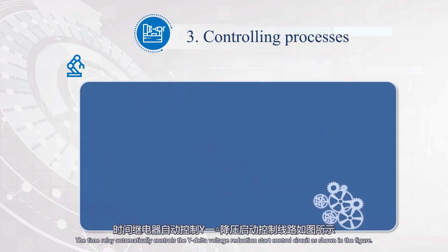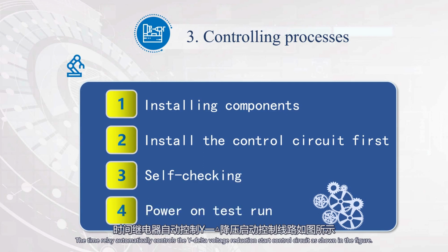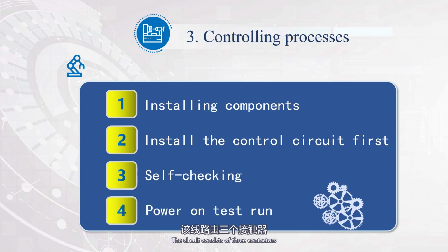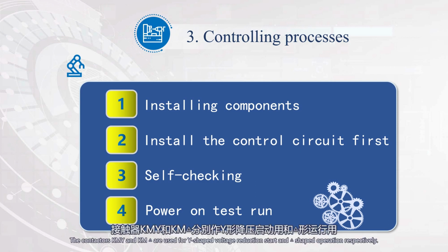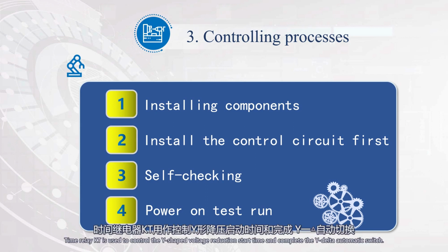The Y-delta reduced voltage start control circuit is as shown in the figure. The circuit consists of 3 contactors, 1 thermal relay, 1 time relay, and 2 buttons. The contactor KM is used for introducing power. The contactors KMY and KMΔ are used for Y-shaped voltage reduction start and delta-shaped operation, respectively. Time relay KT is used to control the Y-shaped voltage reduction start time and complete the Y-delta automatic switch.